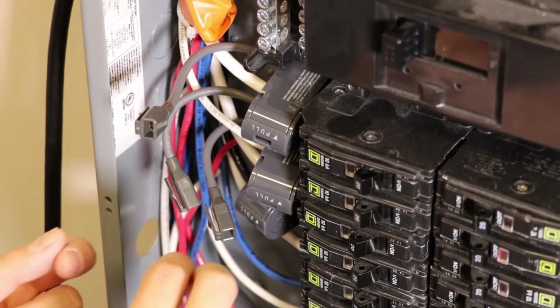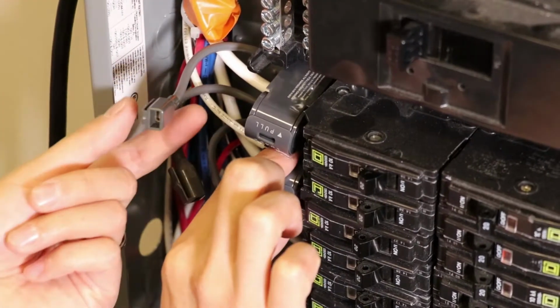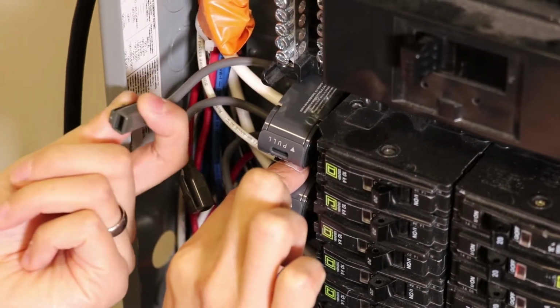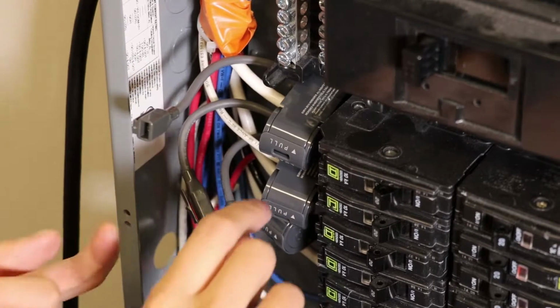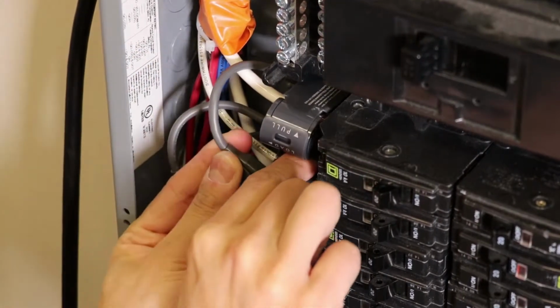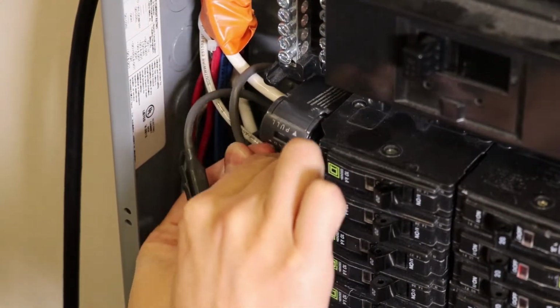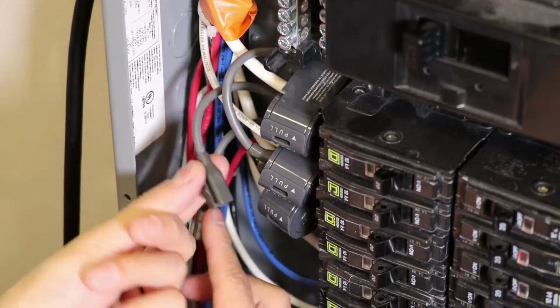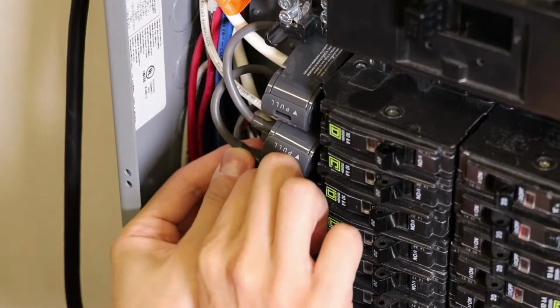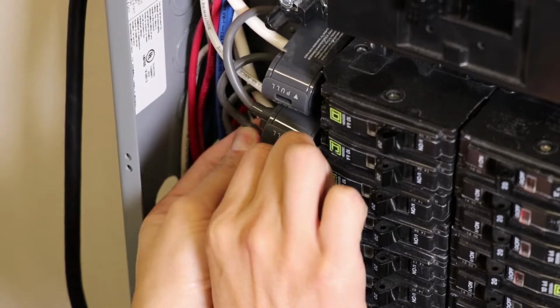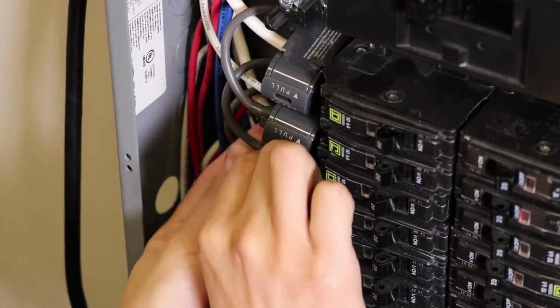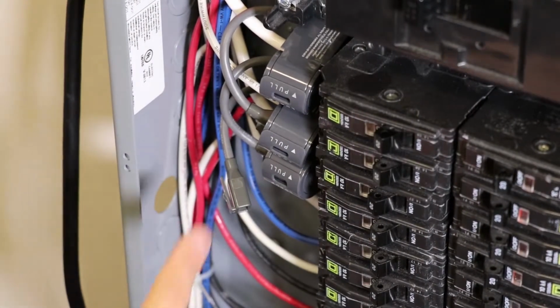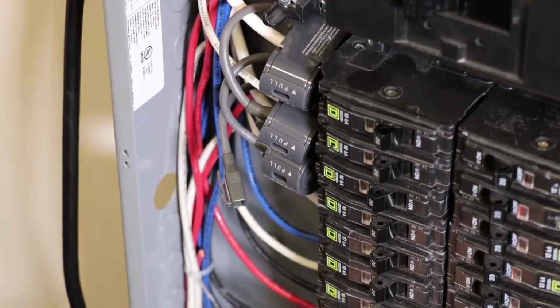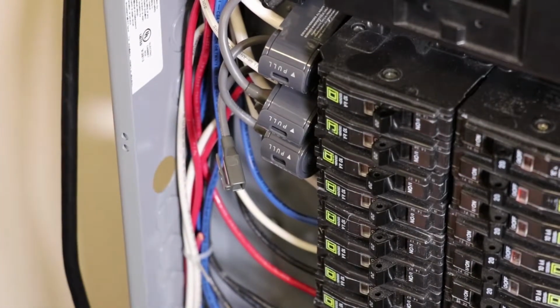After all your current transformers are clamped around the wires, take the output of the topmost sensor and feed it into the sensor beneath it. The sensors will daisy chain so that all the information passes through this sensor chain back to the transmitter unit. You can see we have a gap between our sensors.